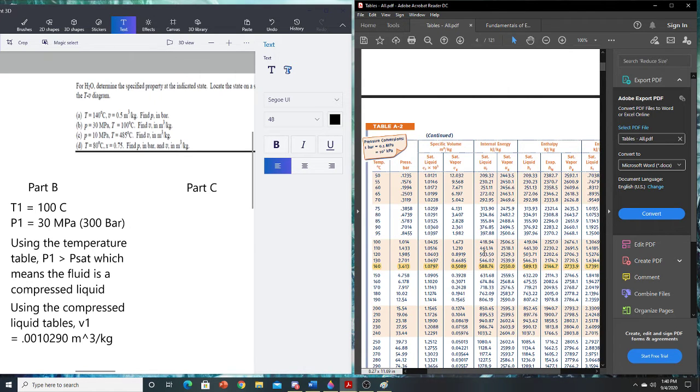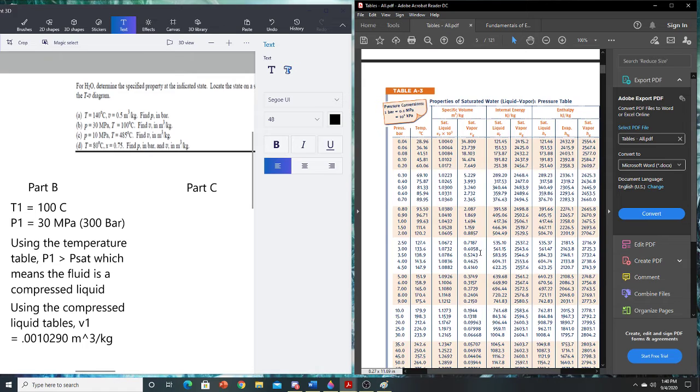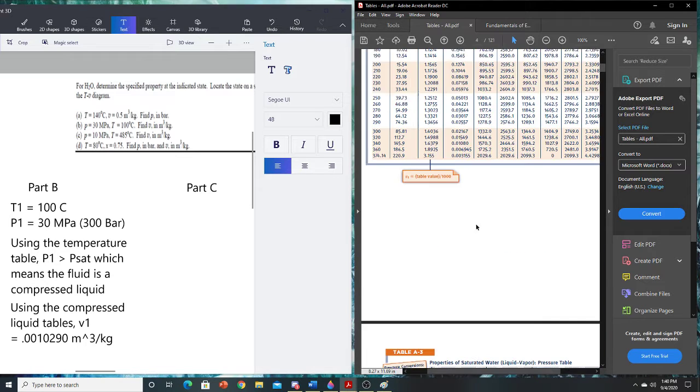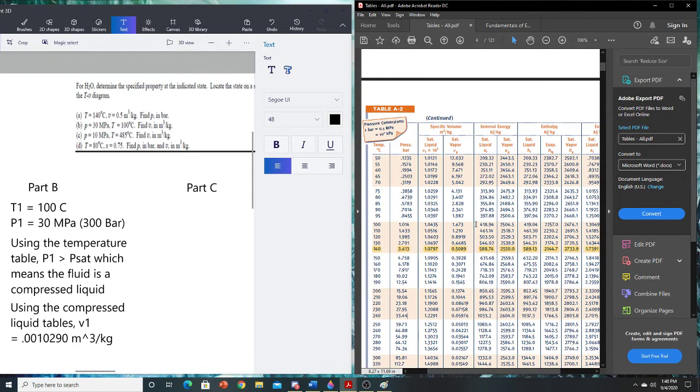So the relationship flips. Essentially, for the pressure table, if your temperature is greater than the saturation temperature, you're superheated. If on the temperature table, your pressure is greater than the saturation pressure, you are subcooled. So you end up on either side of the extreme depending on what table you use. Essentially, it's the flip. One of them tells you one. Now, really quickly, if I had it under here, it would be superheated. So that's where you have to understand that if your pressure is greater than this number, it is subcooled.